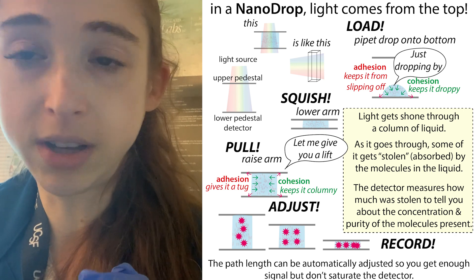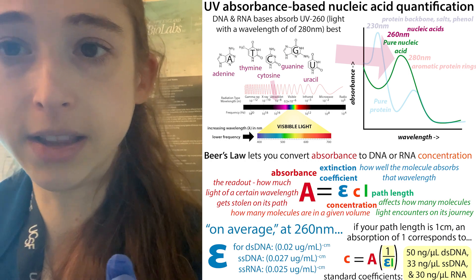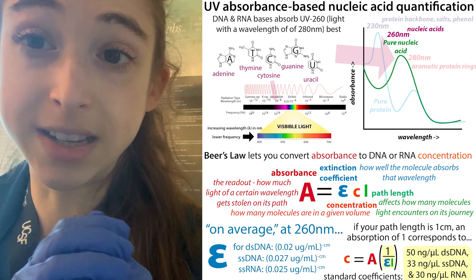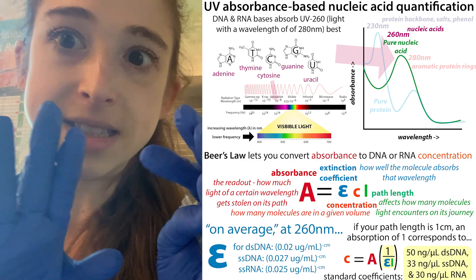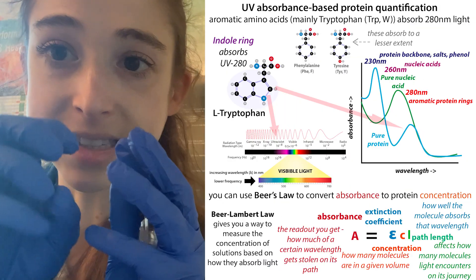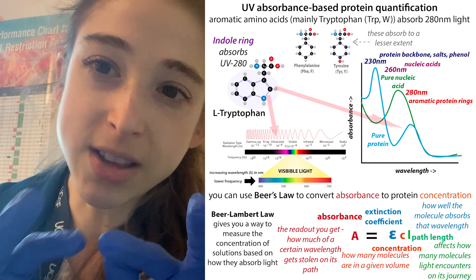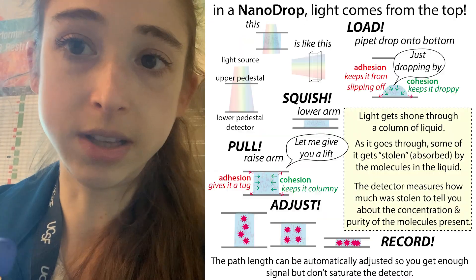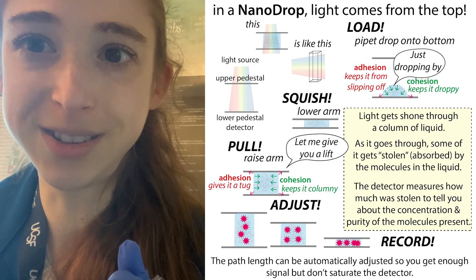So that's the basics of a nanodrop and it's really handy. I'll link to the post on how to actually calculate concentrations based on the extinction coefficient - the nanodrop has built-in standard extinction coefficients for average molecules, but it's going to depend on things like protein size and amino acid composition, since only some amino acids absorb UV light strongly. ExPASy ProtParam is your friend for that. I hope this helped explain how a nanodrop works and how cool it is.